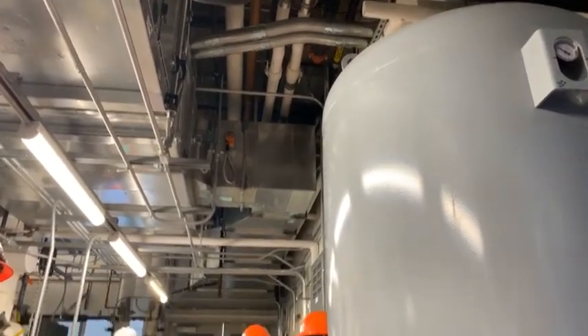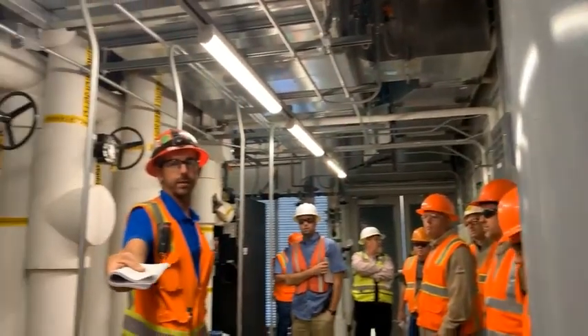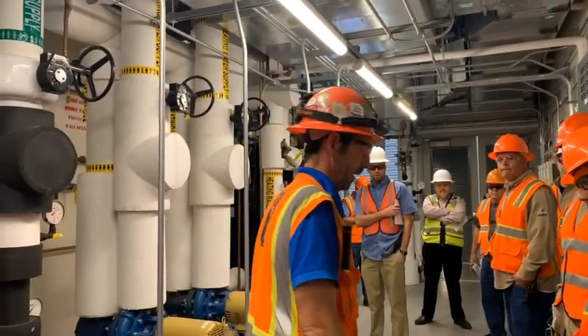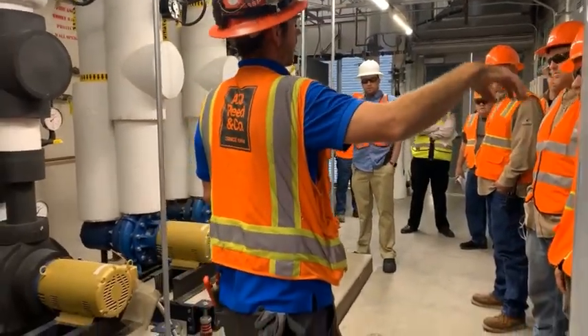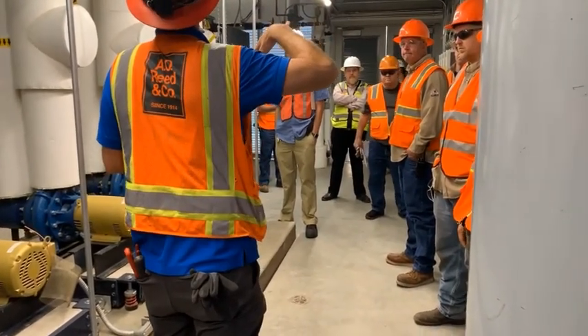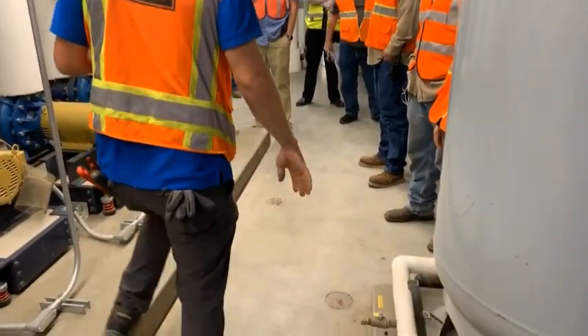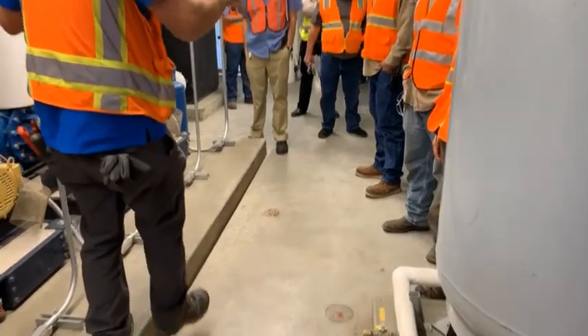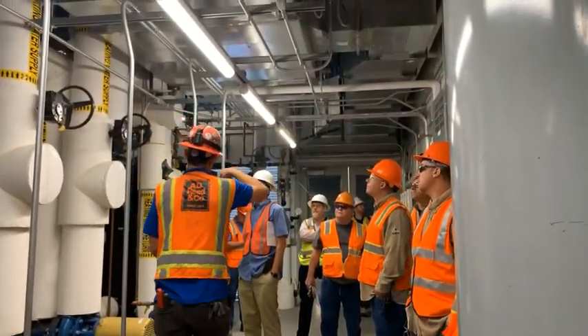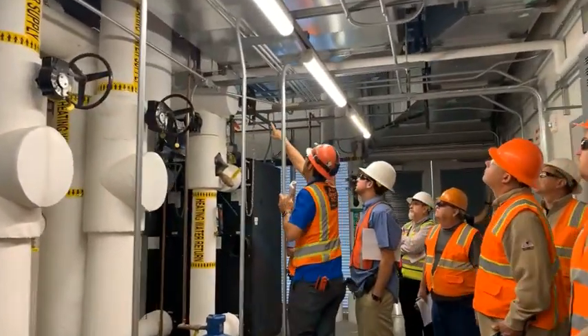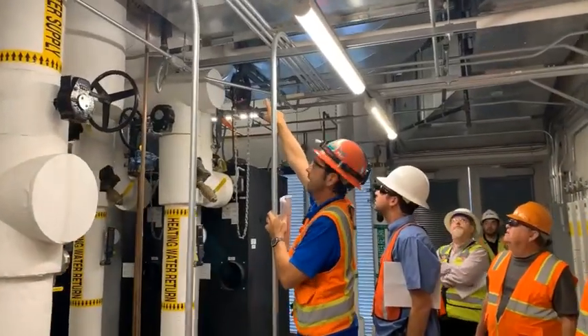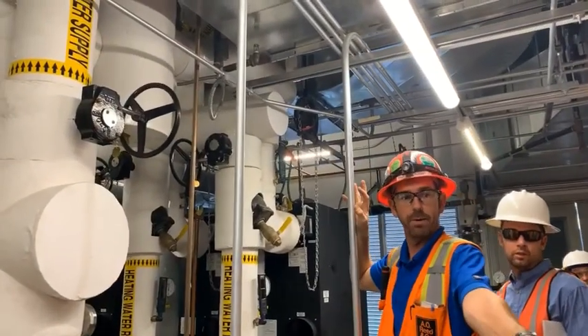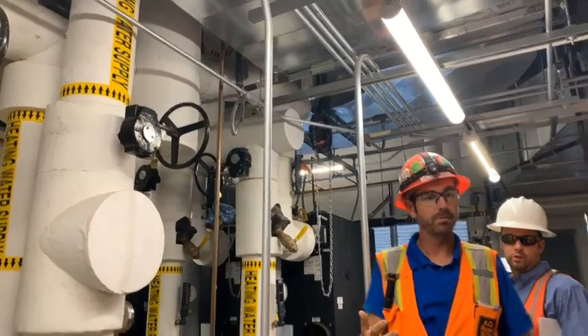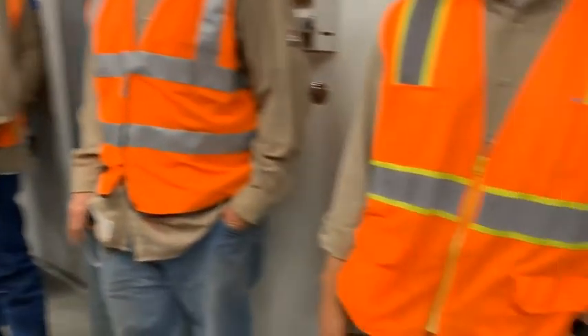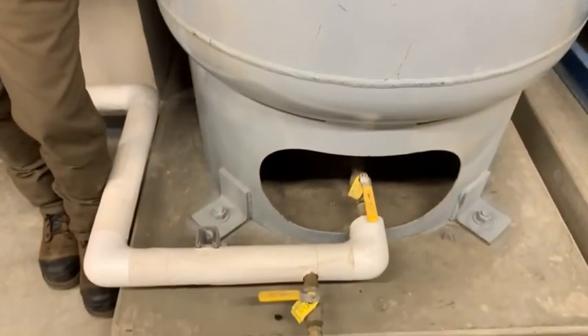We didn't really go over the way to set the tanks. So anytime you set the expansion tank, you have to have it isolated from the system. So here we have a different configuration. This guy ties in over here. We have a shutoff valve up here at the system, okay? We need to use this shutoff valve up here and not the one on the bottom of the tank. First of all, it'd be super hard to drain the tank because the shutoff valve is after our drain, okay? So we need to shut off the valve up here.